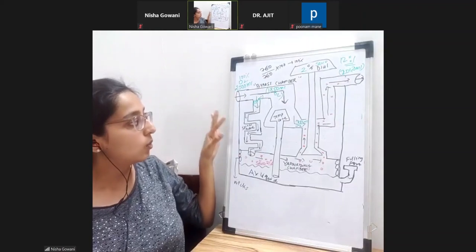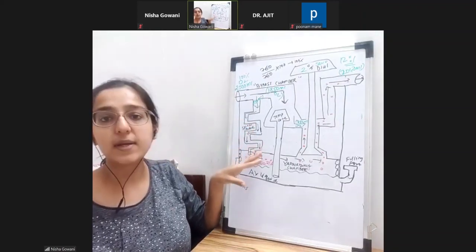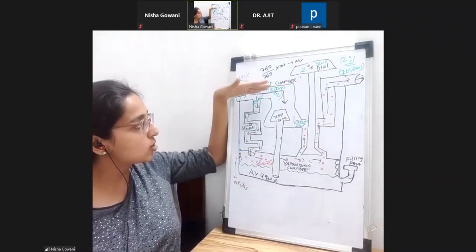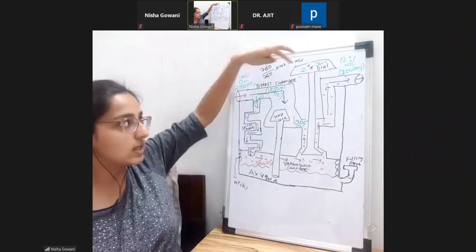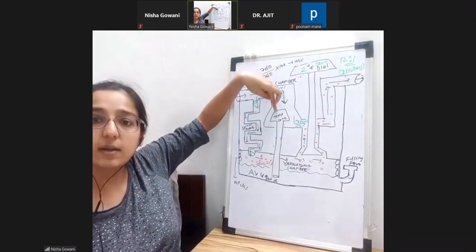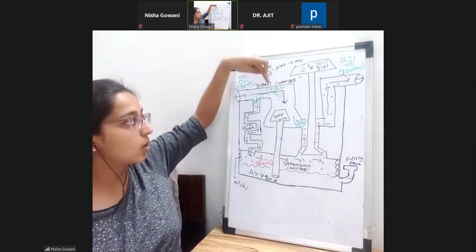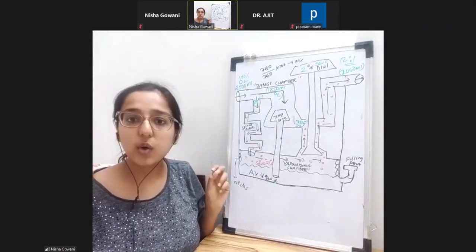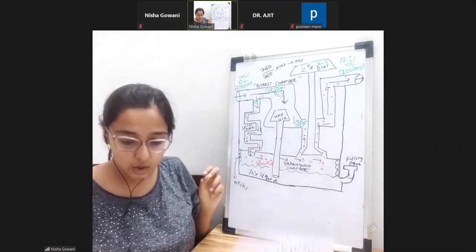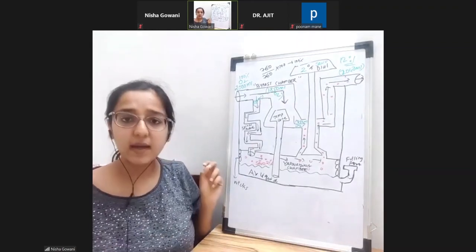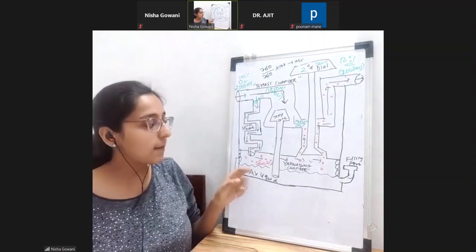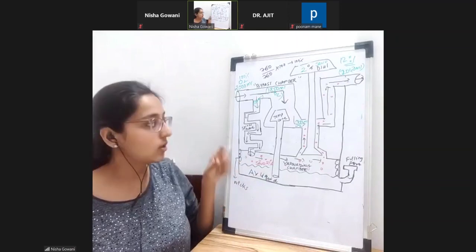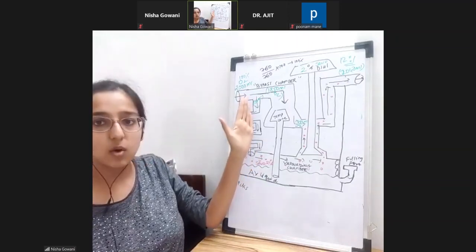What is the role of the temperature compensating cone? This cone also will alter the quantity of how much goes where. Even this determines how much of the incoming fresh gas goes through the bypass or through the vaporizing chamber. As I told you, all our vaporizers are temperature compensated, and all of them are calibrated at 20 degrees Celsius. This temperature compensating cone is made of a material such that whenever there is a change in temperature, the cone will either move upwards or downwards.